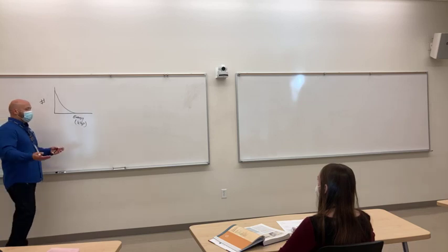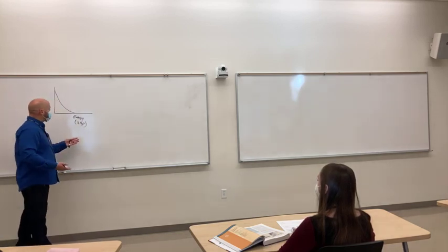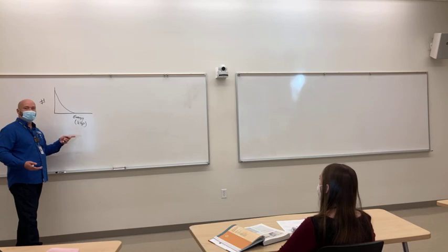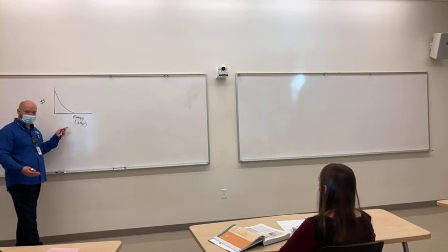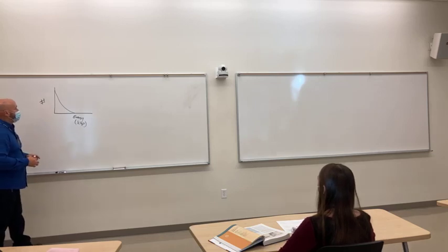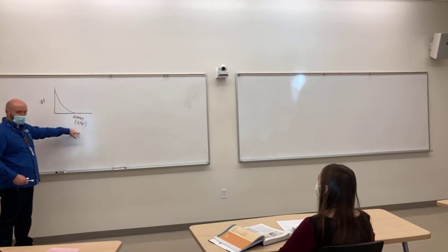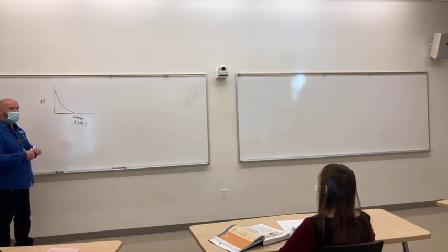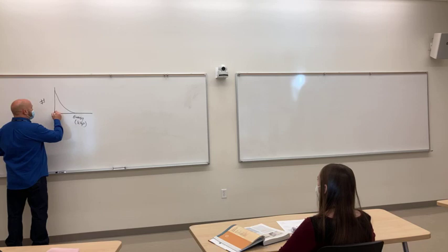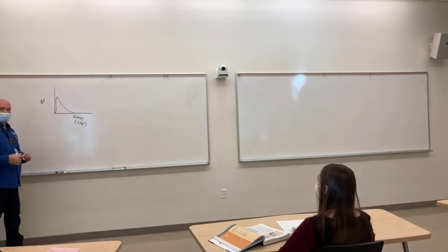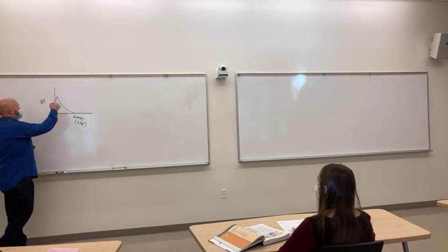So what we know about X-rays, what we think we know about X-rays anyway, is high energy X-rays are going to pass through things a whole lot easier than low energy X-ray photons, right? So what's going to happen is as it goes through that tube housing the high energy photons should remain unaffected, so that as it goes through the tube housing, it's going to take out some of those low energy photons, so our brems spectrum, as it goes through the tube housing, looks like that, okay? So that's housing.